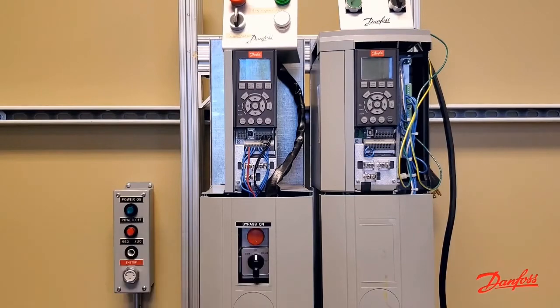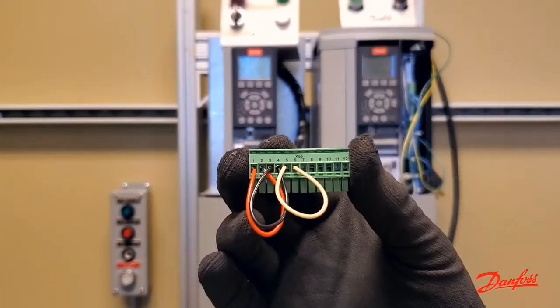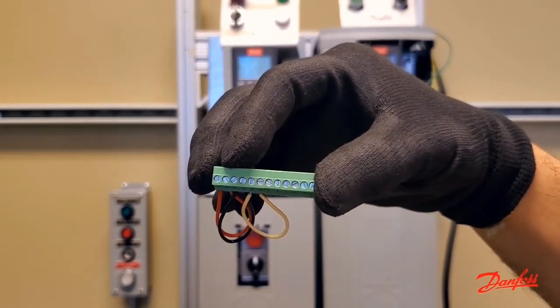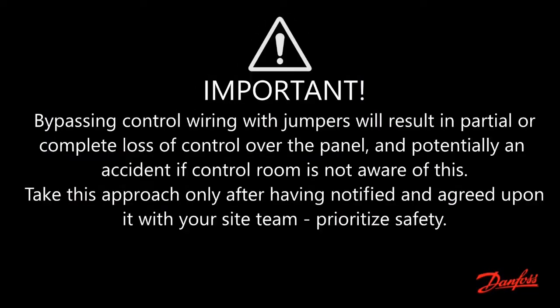One quick and efficient way to test this idea is by replacing all three of those dry contacts with jumpers, which would eliminate the uncertainty. Do keep in mind that by doing this you will be effectively overriding any safeties that may be in place. Make sure you consult with your site team before doing this.